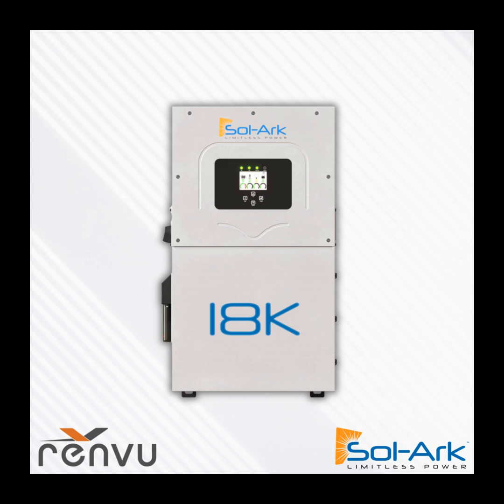2 solar ports. If you really want to, you could get 3 strings into each MPPT, but you'll have to fuse each string, and it's going to be a difficult install. I would just try to stick to 6 strings per inverter for the easiest, best experience.